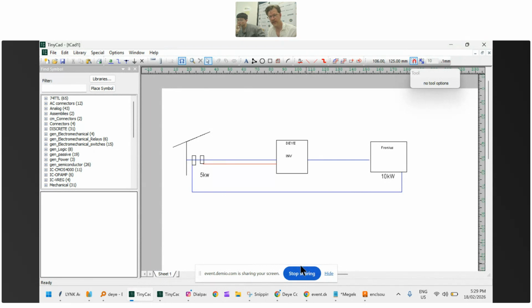It can be done, but it's just when you have export limitations and you've got a larger inverter, it gets tricky. So this would only be if it's a greenfield installation, you would either have the solar array on the Deye and not have an AC coupled inverter, or you would use the Deye like you would a Victron and just have the whole array on the AC coupled inverter if you wanted to do that for some reason. Or you would set it up so that the AC coupled inverter, if you really wanted to have solar on both, you'd set it up so that AC coupled inverter wasn't any larger than the export limitation.